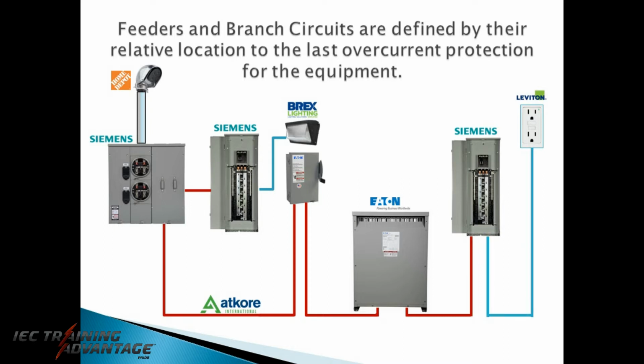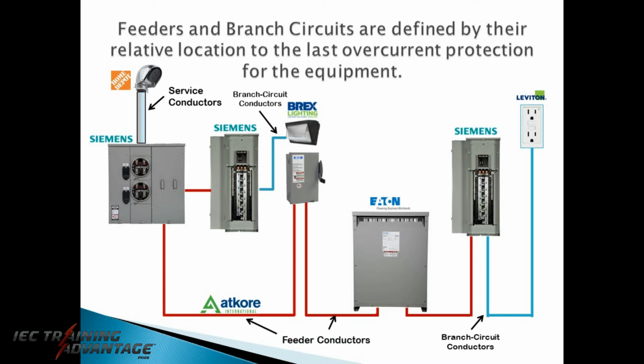So let's look at the different types of conductors we have here. We have some branch circuit conductors. We have service conductors. And now let's identify these feeder conductors. They're all the conductors between the service and the last overcurrent protection devices. So we have some here, and here, here, and there. Now, these conductors that we pointed to that are next to this transformer actually take on another definition. They are transformer secondary conductors, and they have additional rules that apply to them.